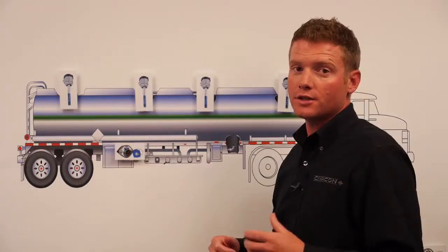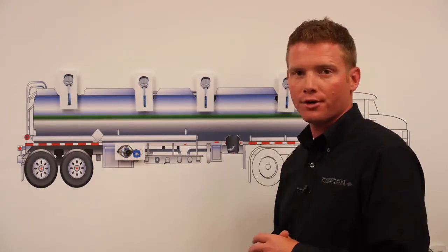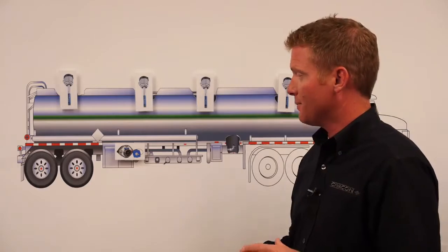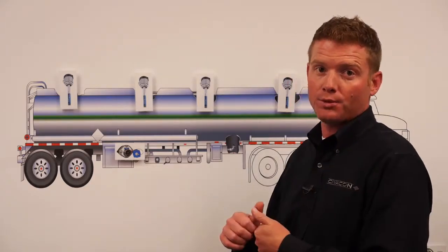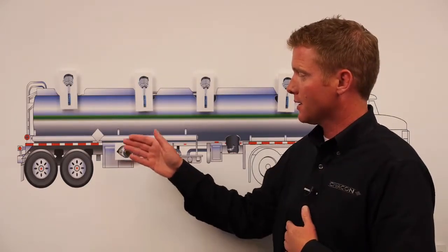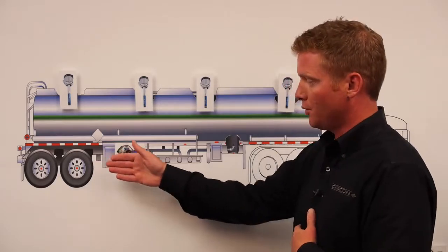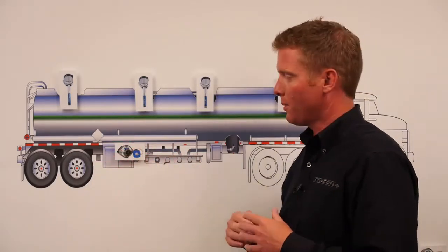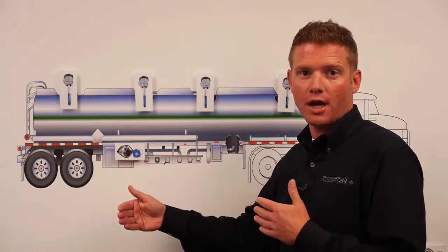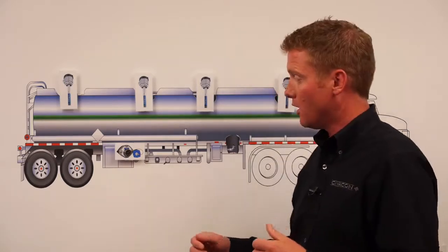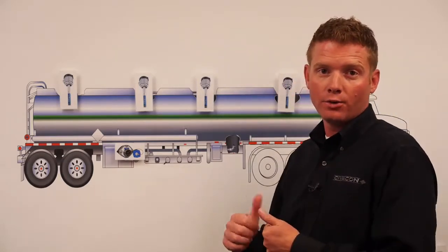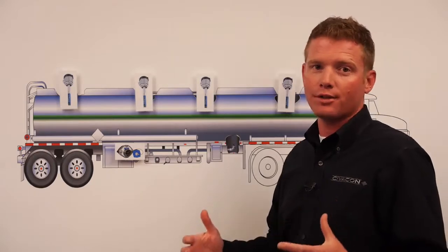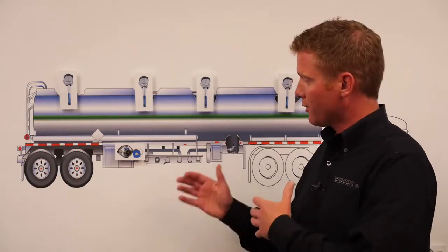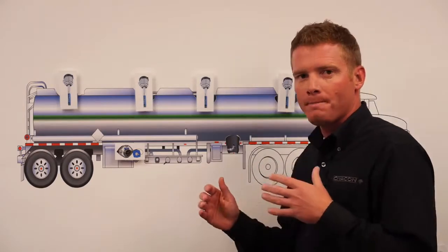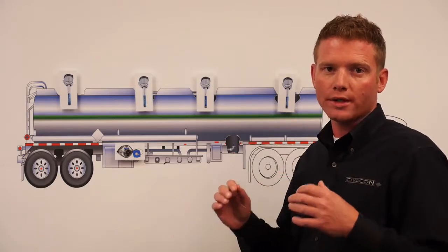Some of the disadvantages of not having an onboard monitor on a 5-wire system is you can't have multiple sockets, meaning multiple optic thermistor sockets. You can have multiple optic sockets, but you won't be able to have an optic and a thermistor socket without an onboard monitor. Also, you're not going to get the ability to have retain, and you lose a lot of the troubleshooting ability. You got to remember these trailers are powered by the rack or a test fixture.